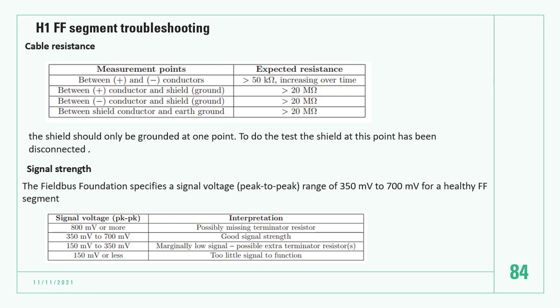Okay. Next, we talk about troubleshooting. First is the cable resistance. You should measure how much resistance. Before you measure, the resistance is between positive conductor and shield, negative conductor and shield. You should disconnect the shield at the end point. We are to test, so the shield at the point should be disconnected.